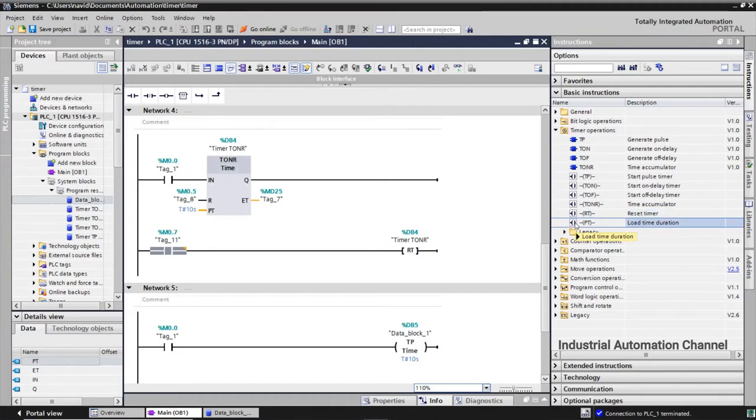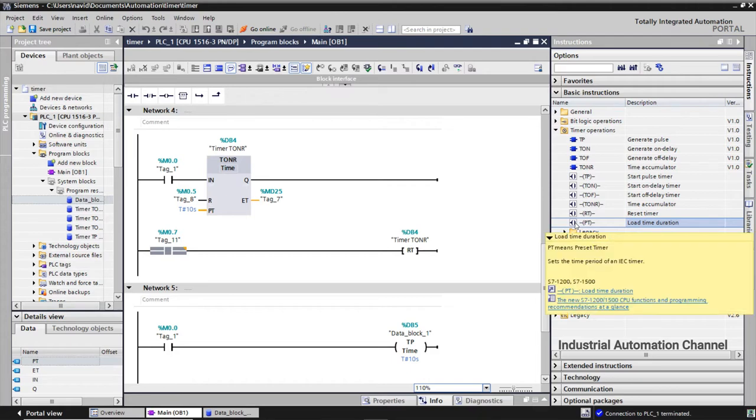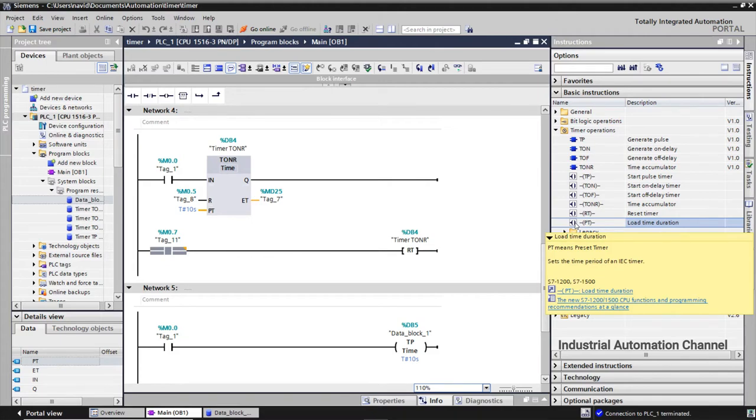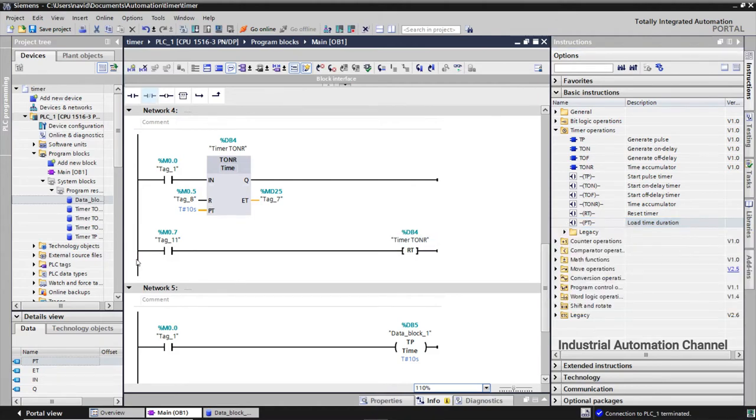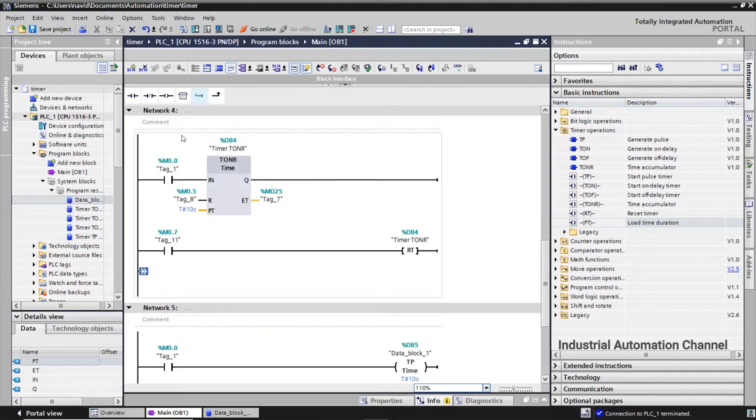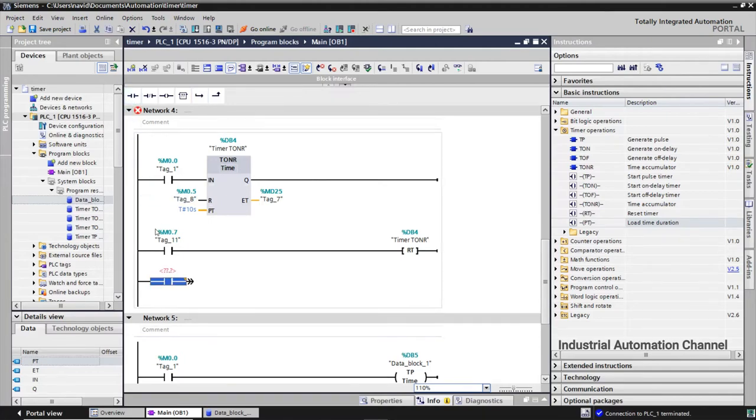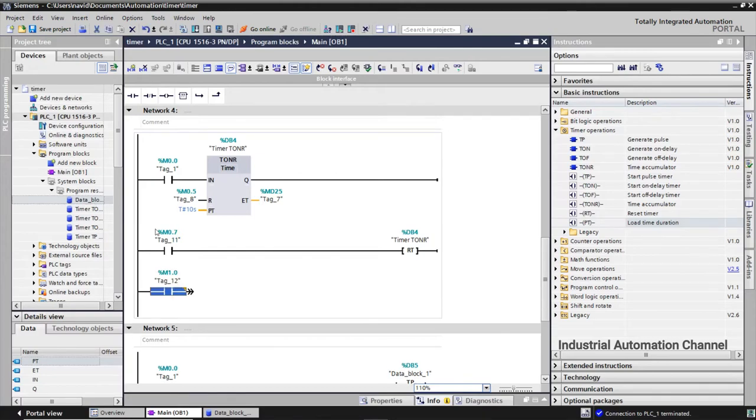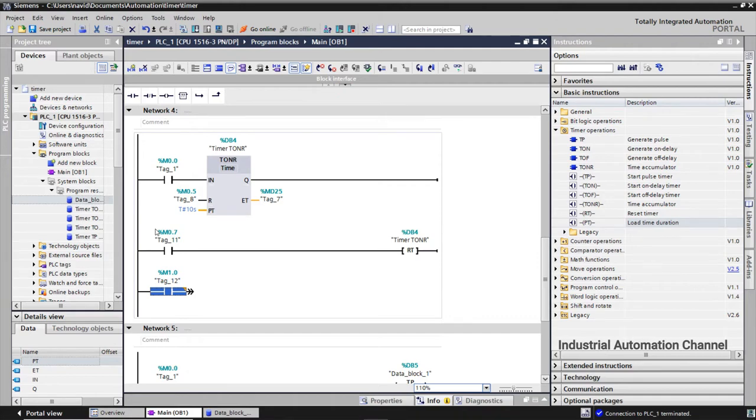The next instruction is load time duration. With this instruction I will show you how to change the preset value of timers dynamically. Suppose our PLC is in run mode and the program is running. If we want to change the time we need to stop the PLC and change the program and again download and run PLC. But we want to change the preset value while PLC is running and without PLC stop and program change. As you know every timer in TIA Portal has a data block to save its data like preset value. We can read and write the values of this data block in our program.